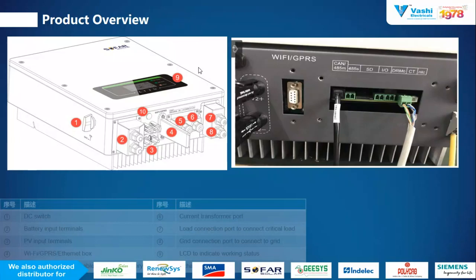Sixth is the CT connection for the load current measurement. Seventh is a load connection port, a critical load connection, meaning emergency condition, that I already explained. So this load is on a higher priority. The critical load is always on a higher priority for hybrid inverters, because it is required all over the day, even when your PV is not available or your grid is not available. The eighth connection is the grid connection port or normal load connection, the ninth is the display, and the tenth is the exhaust valve. So these are the pointed out figures of the different connections that we have in the hybrid inverter, as well as the display and BMS system.